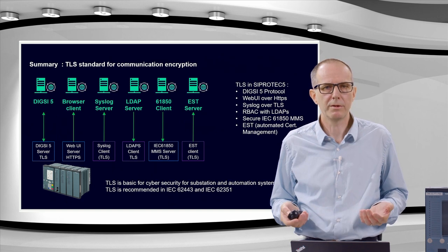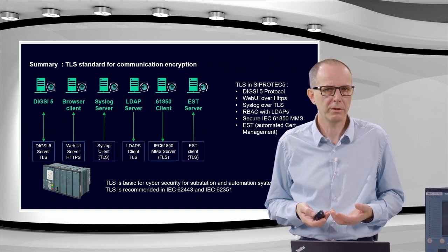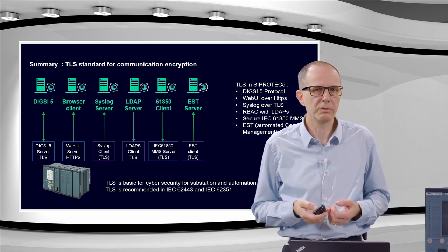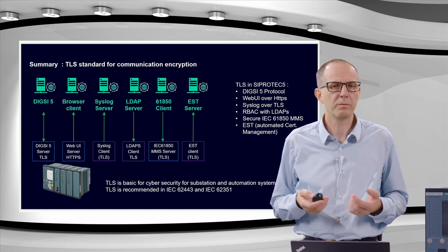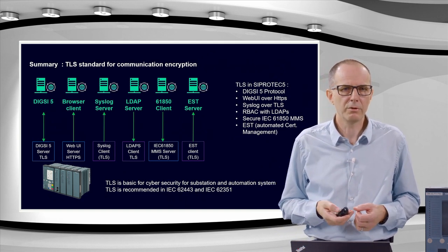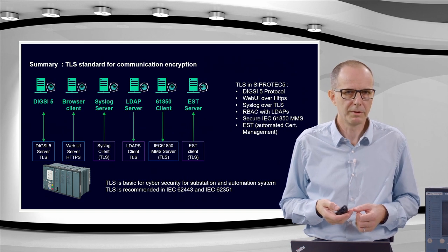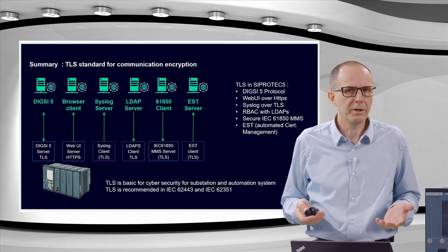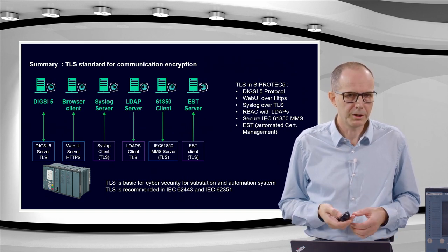We also implement the automated certificate management as recommended in the IEC 62351-9. And the protocol there is called EST, that stands for Enrollment over Secure Transport. And it's based on TLS with mutual authentication.